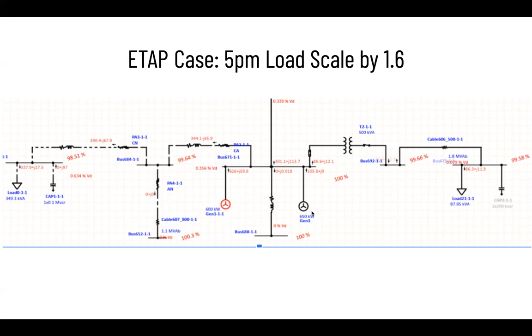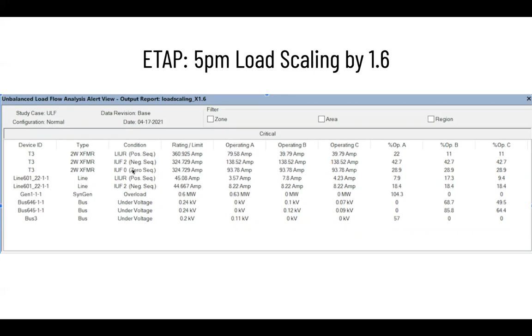Here, this is once again the same case from the same hour, but this time we're upscaling our loads by 1.6. You see in this example of our load flow analysis that our battery is indicated in red. This means that our battery won't be able to deliver what our load is requiring. So from this, we can determine that we will need upgrades, upgrading our battery, maybe doubling the storage of it. And as you can see, these are also the violations for that case. Once again, here we can see the overload on our battery.